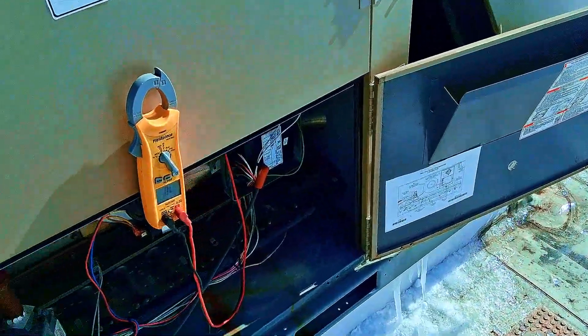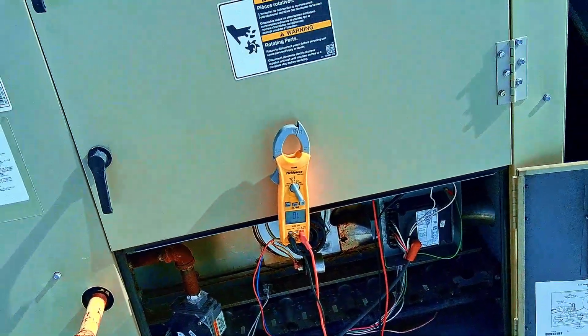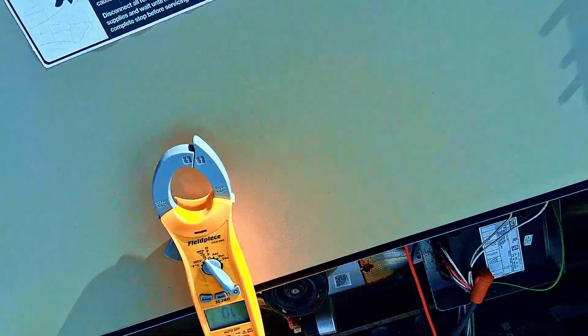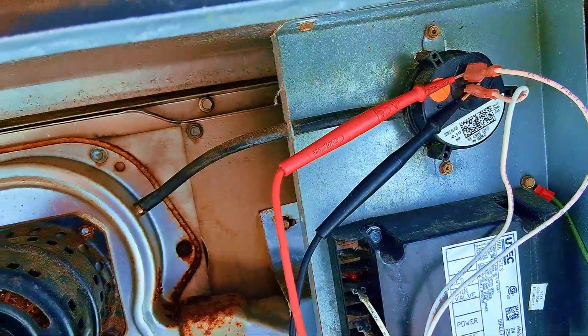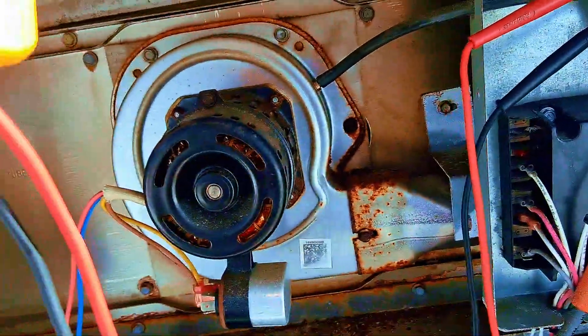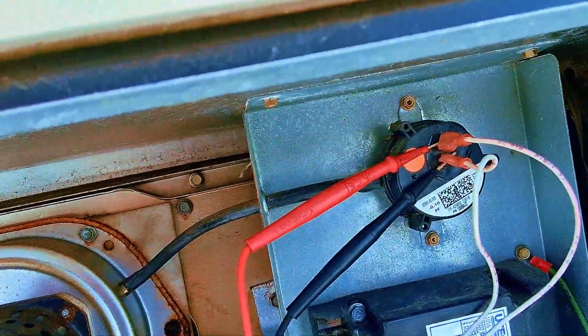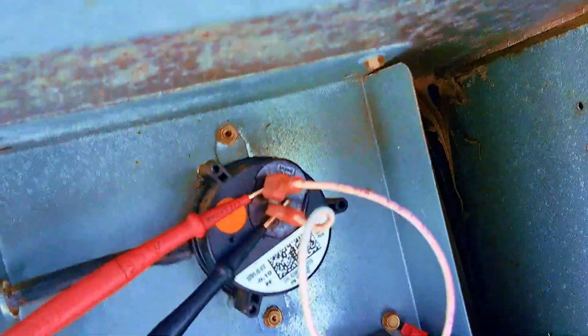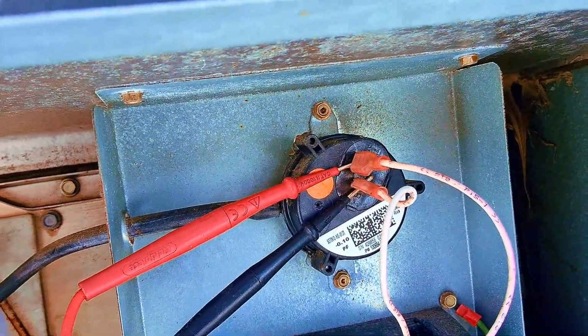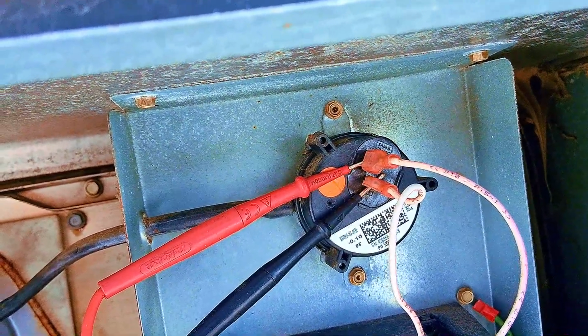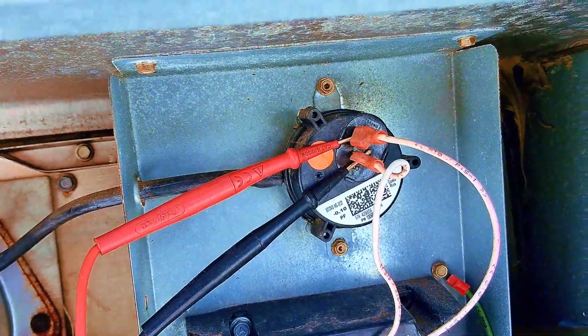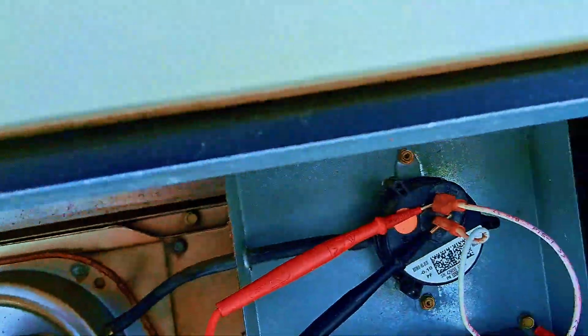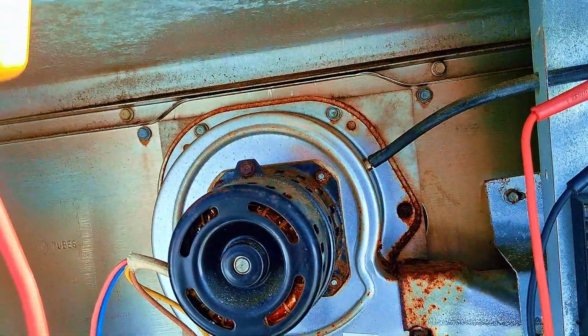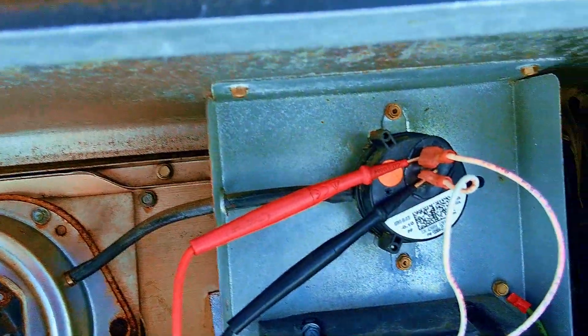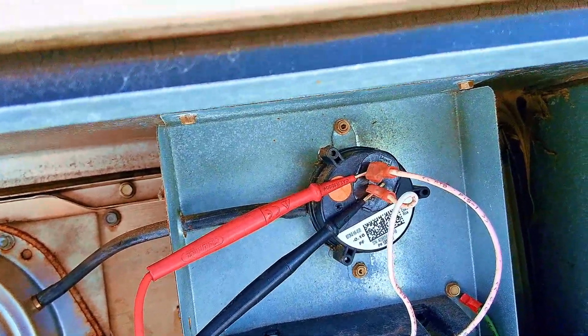Alright guys, after some research, reading up on this Lennox unit, it says basically what's happening, because I'm trying to figure out why I'm still getting some kind of continuity even when it's not calling for heat. It's saying that when it's calling for heat, even if the inducer motor is not on, the board is going to send a small microamps signal through the system to verify if the switch is open or closed. My meter's gonna pick that up. They say it's small enough for me to pick it up on a meter, but not large enough to confirm that the inducer is running.